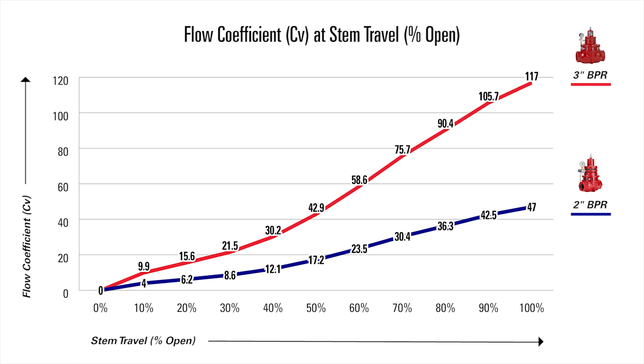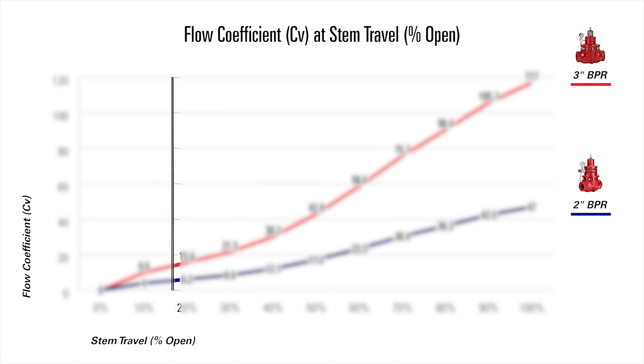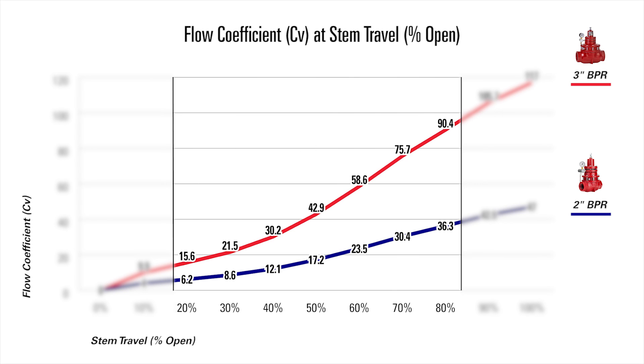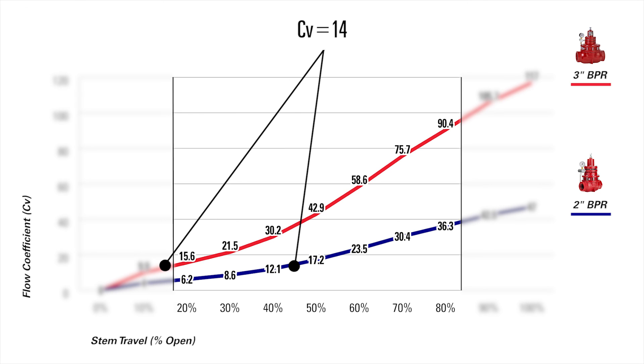We recommend you select a valve for which the CV falls between 20 and 80% open stem travel. For example, if you used our valve sizing calculator and came up with a CV value of 14, you would want to choose the 2-inch valve, because in the 3-inch valve, 14 would fall outside of the recommended range.